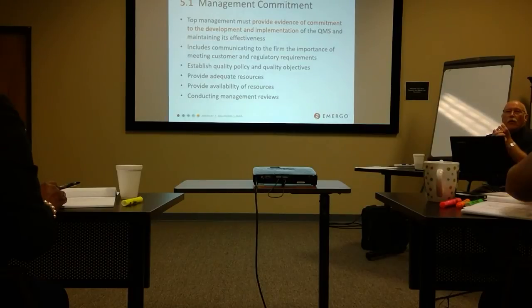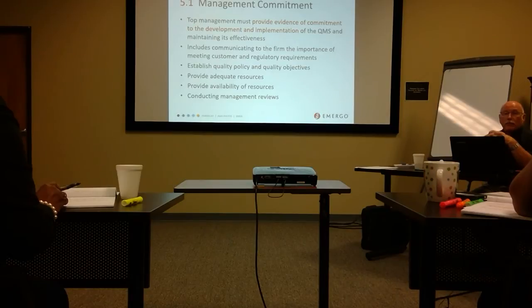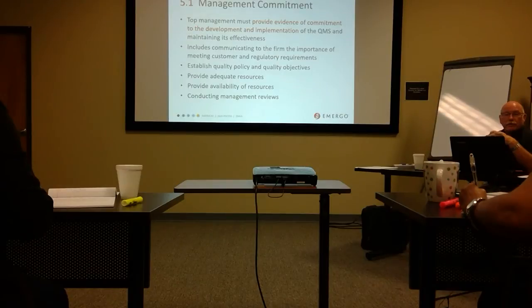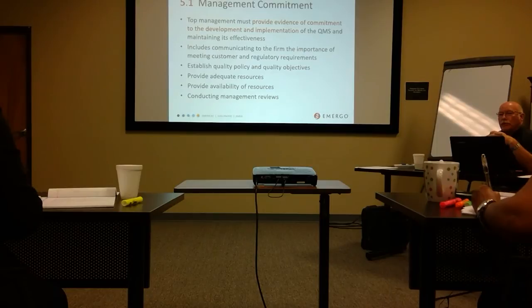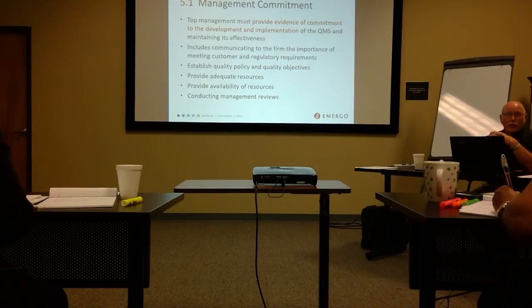All right, chapters 4 and 5 are fairly straightforward. Both are fairly short, but critically important. The big hitter in chapter 4 is change control. In ISO it's 4.2, now 4.2.4; it used to be 4.2.3. I tell my FDA people this all the time: if you do nothing else right, make sure you get change control right, because if you don't, the FDA will rapidly conclude that you're out of control and then really bad things happen: consent decrees, all kinds of unpleasantness.